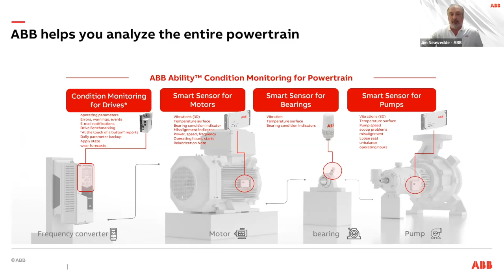And then also we've got condition monitoring for the drives. All this information can be brought through the drive. The drive itself will tell you a lot of the performance behavior that's going on in the motors. It will tell you the energy being used, the cycle time and the temperatures, as well as give you some good warnings and notifications if there's a problem with the variable frequency converter.